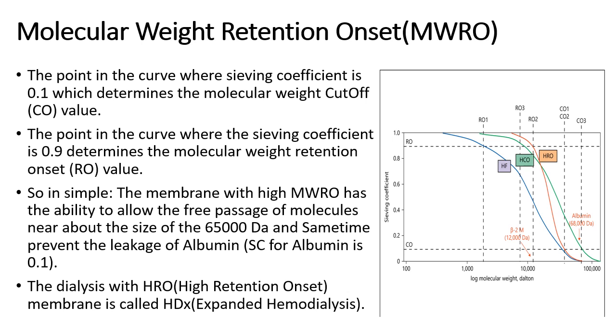Finally, molecular weight retention onset, or MWRO, is a relatively new concept in membrane technology. In the graph, three types of dialyzers are shown — high flux, high cutoff, and high retention onset — according to their sieving coefficients. As molecular weight increases, the sieving coefficient decreases. The high retention onset, or HRO, membrane allows clearance of molecules up to 65,000 daltons, while preventing albumin leakage with a lower albumin sieving coefficient of approximately 0.1. Dialysis using an HRO membrane is known as HDX, or expanded hemodialysis.